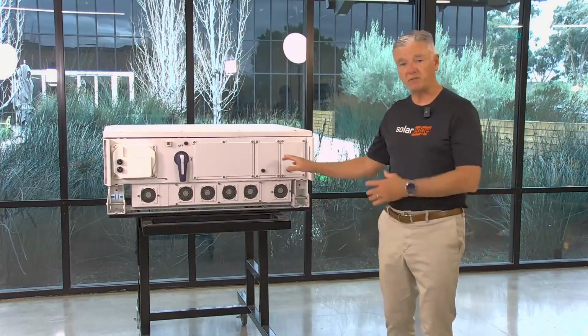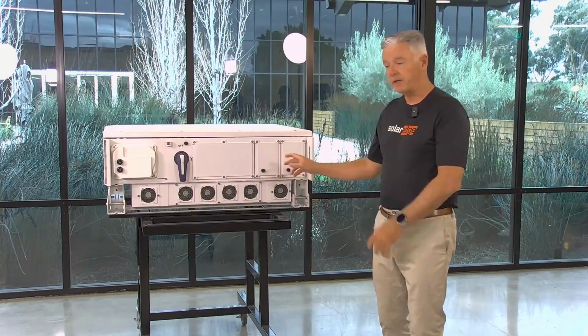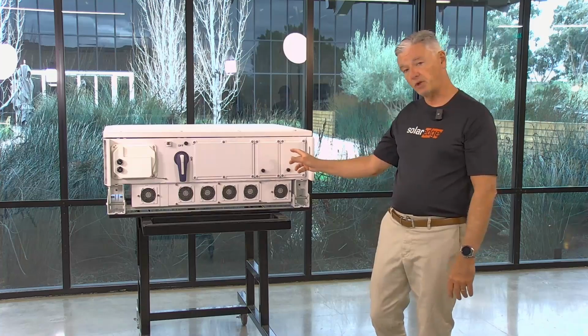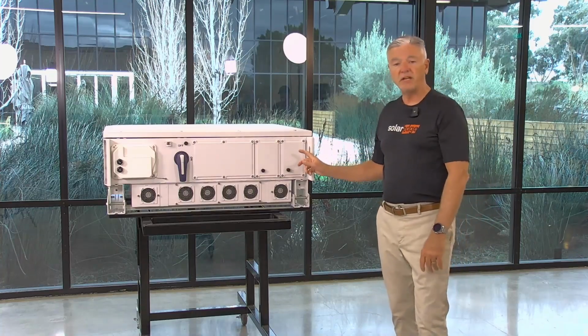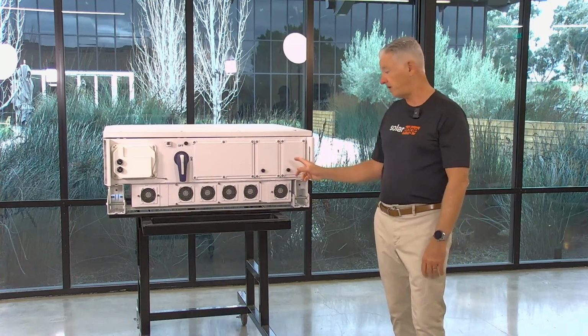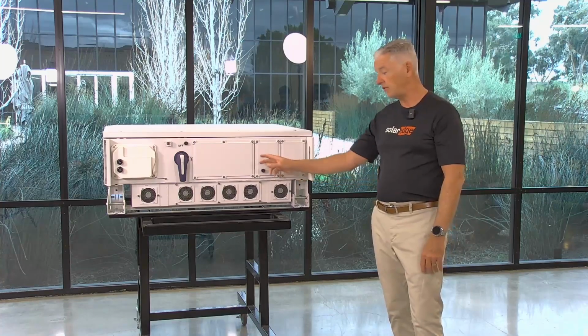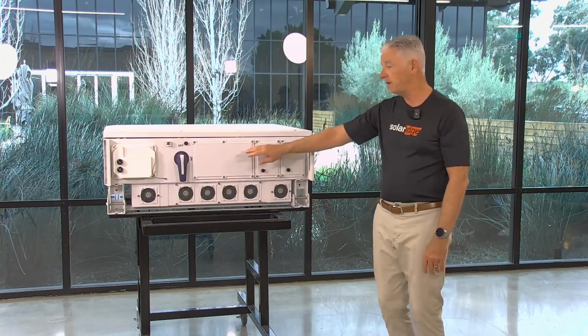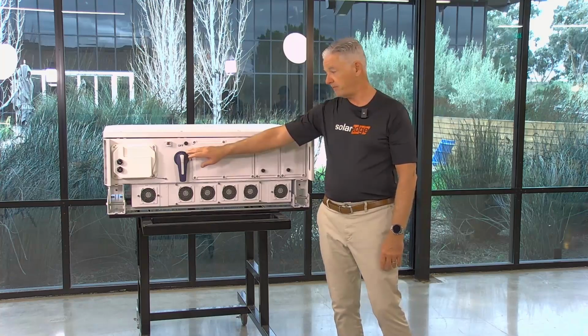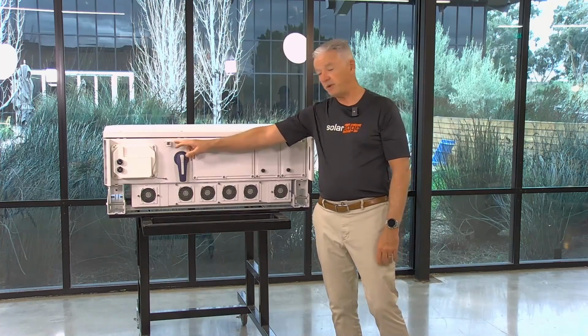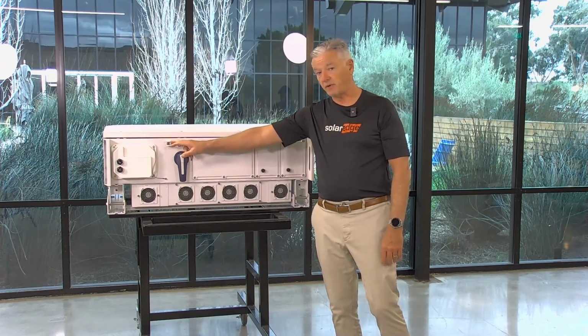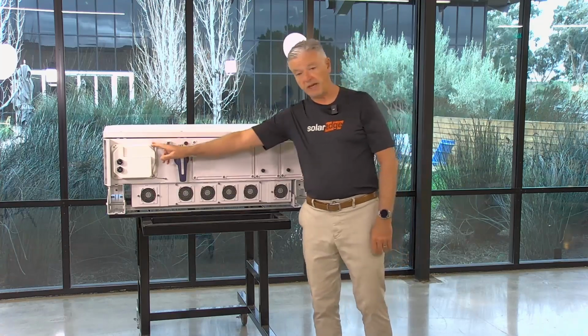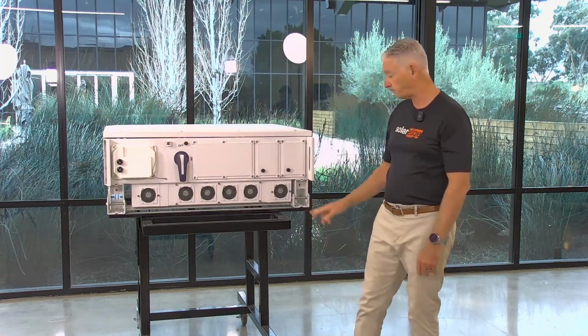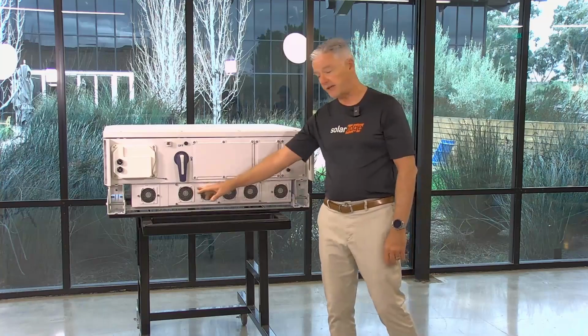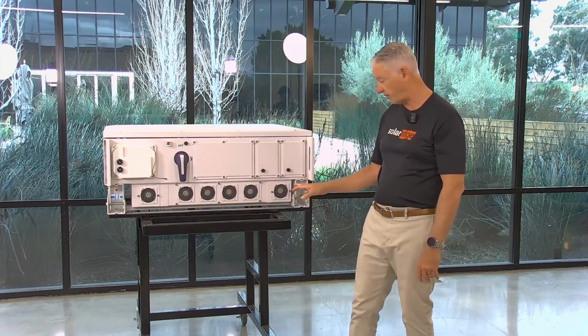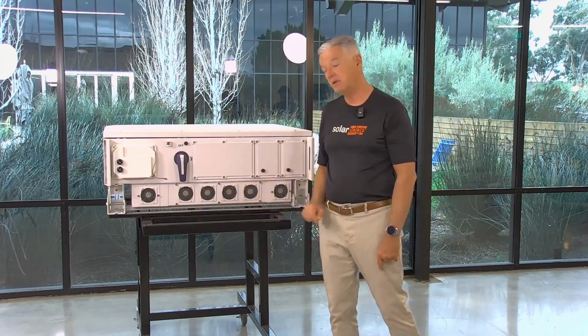For illustration purposes, we've flipped the inverter on its back. Here you can see what the bottom of the inverter looks like. From right to left, you can see the two AC conduit plates, the DC conduit plate, the DC switch, the pairing switch, which is used to pair the optimizers and to put the inverter into service, and the communications module. Also, you can see the 6 fans on the bottom that are used to help cool the inverter, and these are field replaceable.